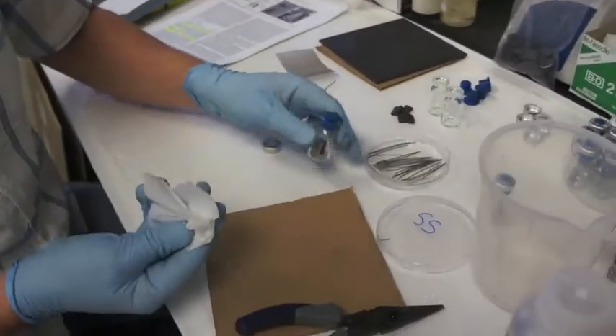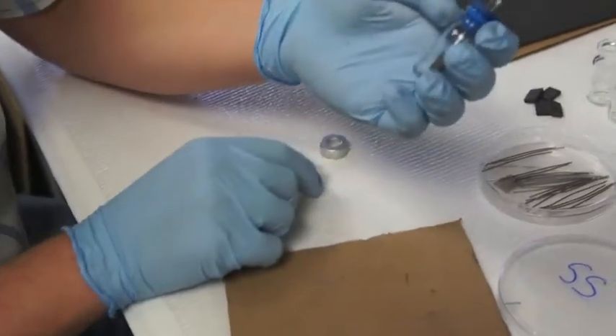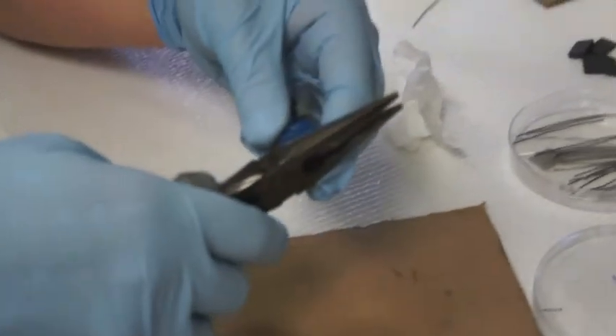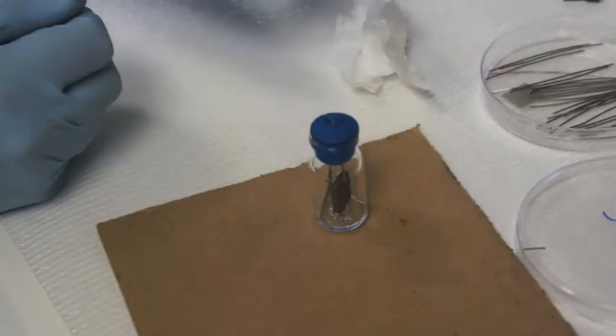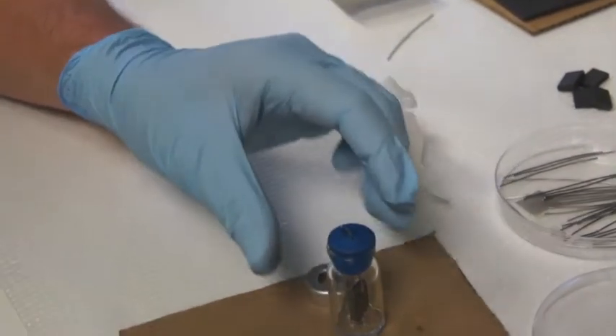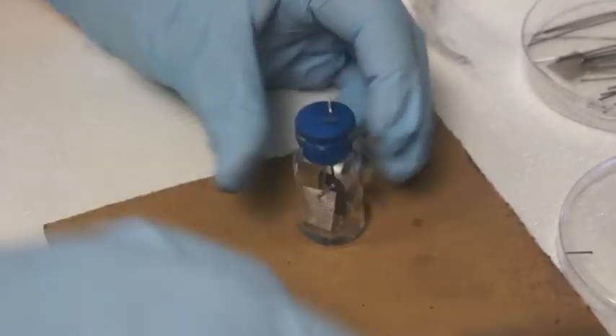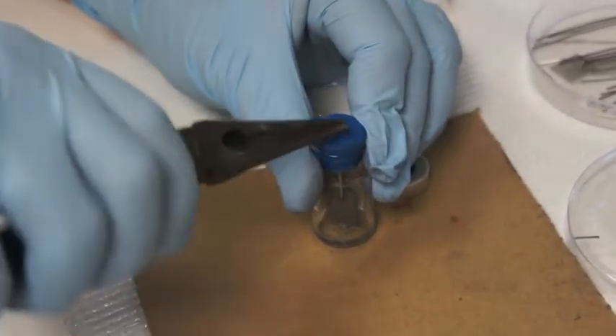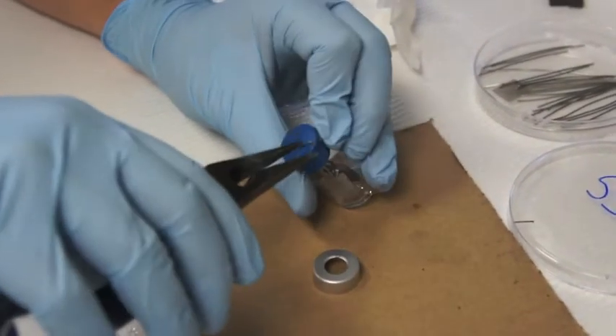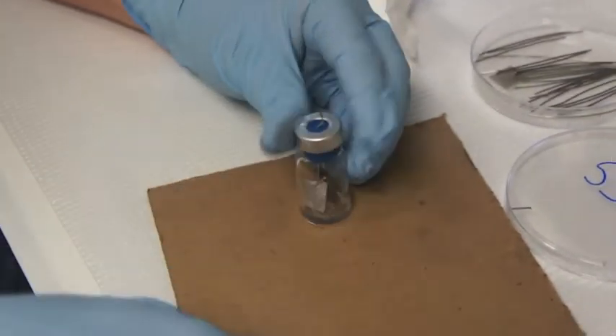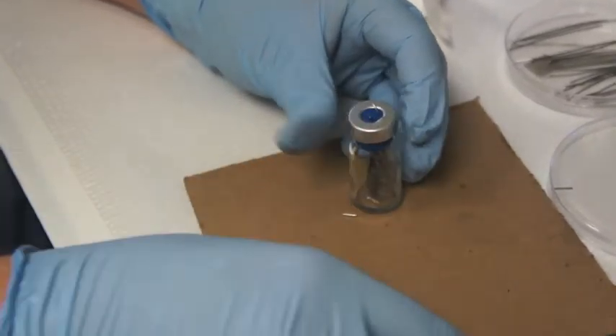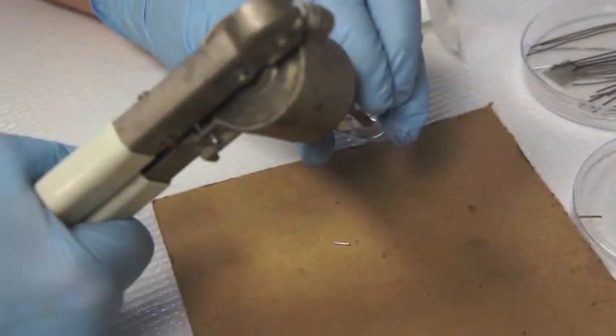Sometimes I find it helps to use a napkin or chem wipe. Gives you a little extra friction there. So now we've got our electrodes in there. Trim off the wire just a little more. And the next step is sealing it with our aluminum crimp cap. So to make it easier, what I do is bend the wires down. Put the crimp top on. I might need to lift this one up here first. Now bend them down. So that you can get the crimper. And then now you can bend the wires back up.